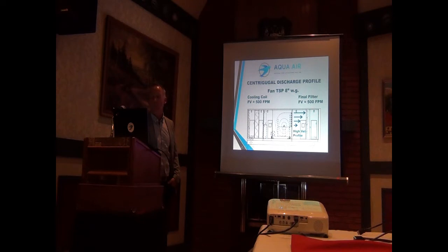If you look on the downstream side of things, why is the profile important? Well, the fan is sucking DW, DI, dual inlet, dual width wheel, most common. It's going to be drawing off more of the center of the coil here and the side. So if you were to look at it like this, you might be getting what, 40, 50% of your coil.